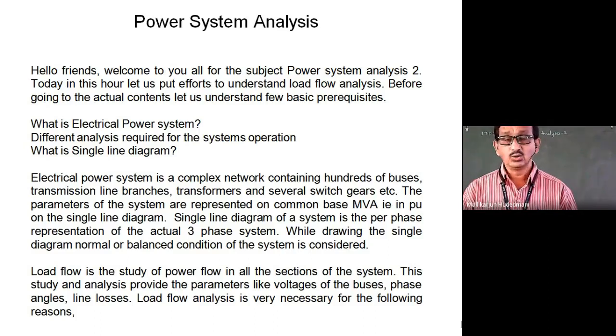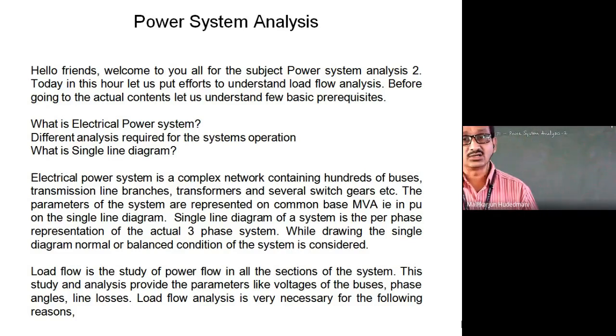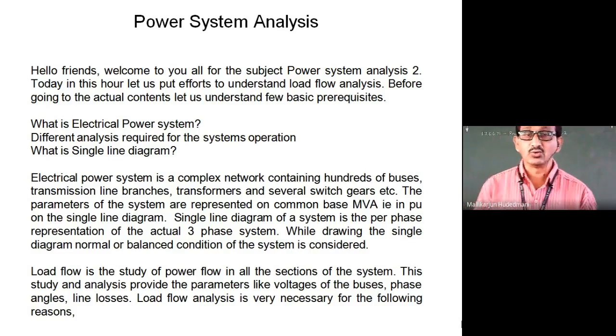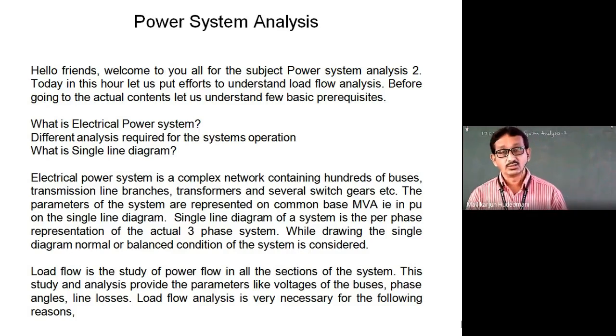Is any transformer loaded beyond its capacity? Is any transmission mechanism stressed beyond its transfer capacity? Or is there any transmission line suddenly out, due to which the other alternative lines are getting subjected to high work pressure? This is how the state of health of the power system, from the perspective of power flow, is to be studied. That analysis is very necessary for us.